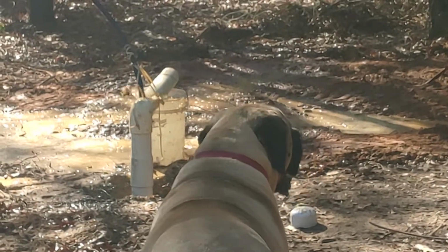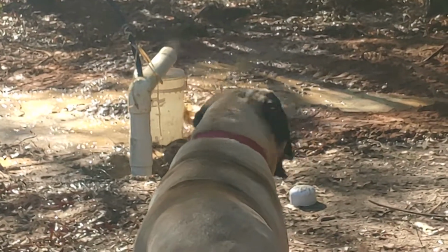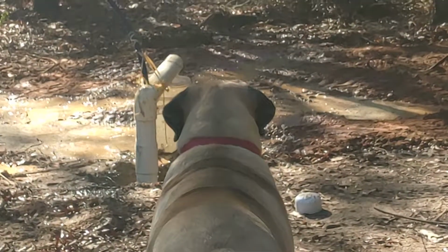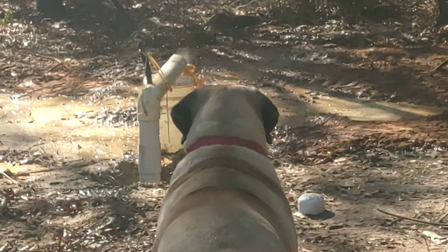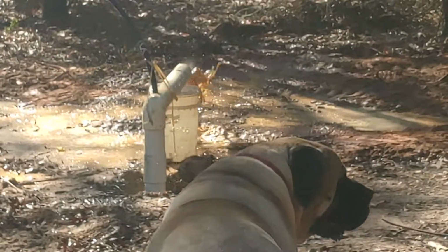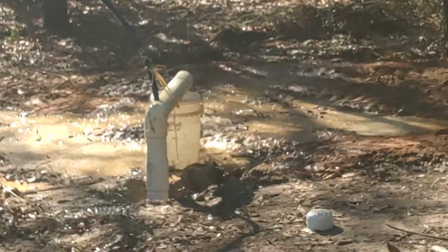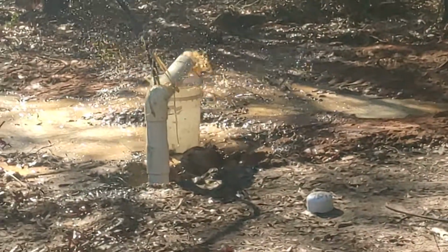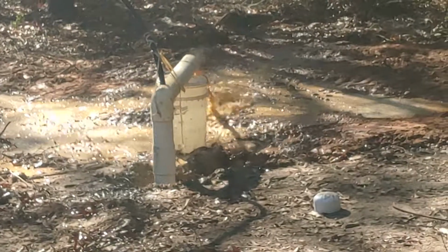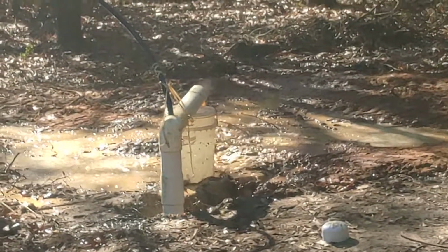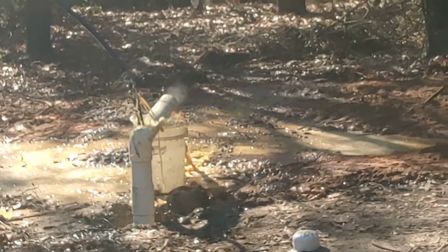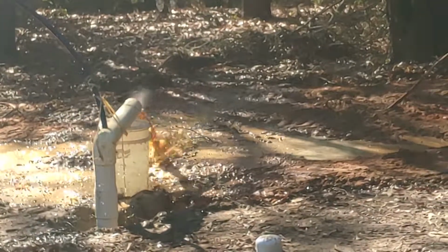The thing is, when you put air in it, a lot of times it'll overcome the head pressure that we're talking about, and it'll push some of it back. So it'll pump more than it jets. So it'll actually produce a lot more. However, whatever we physically see, because we don't know exactly what that differential is, because everyone's different, we only size our pumps for what it'll jet. Therefore, we know it'll pump more, therefore we know it'll never, ever outrun your well, because I know it'll produce more than what the pump will put in it.